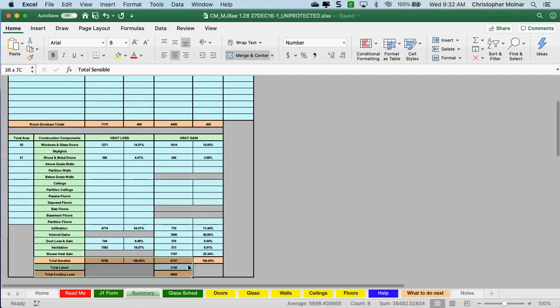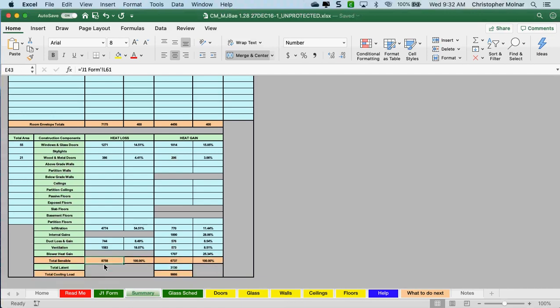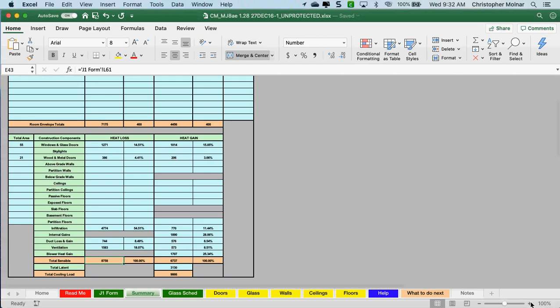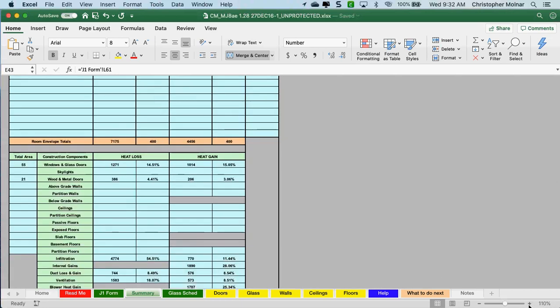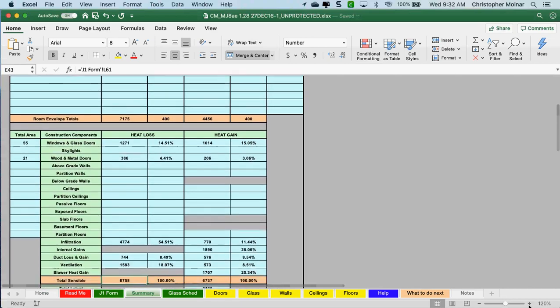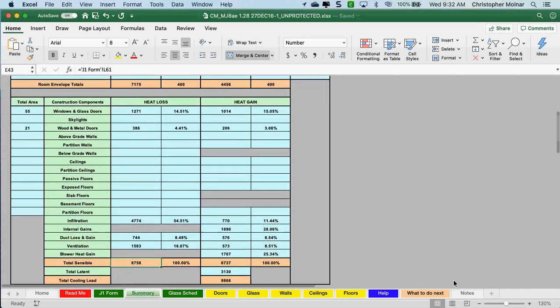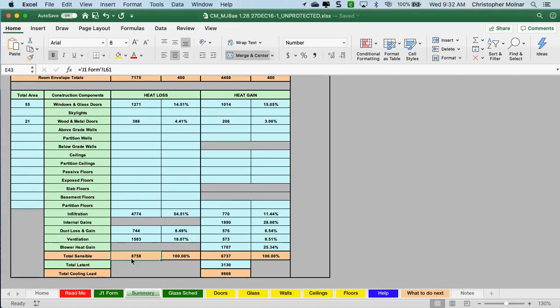The summary page down here on the bottom is where we're talking about totals. Your total sensible load on the heat loss column — my number is 8,758. I don't have my whole house in here. That's your sizing of your furnace for that area.